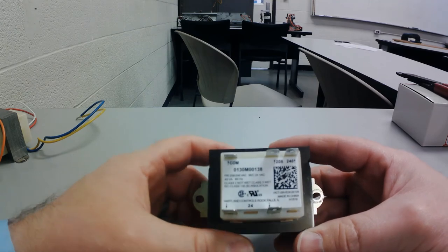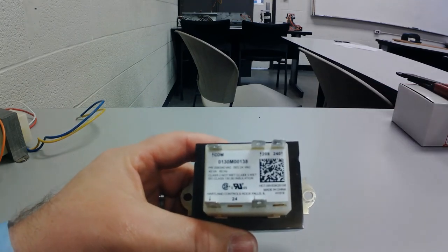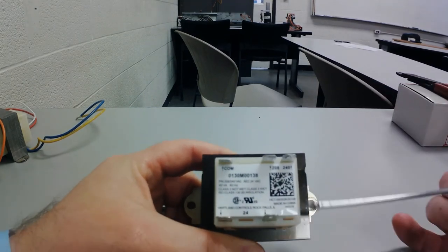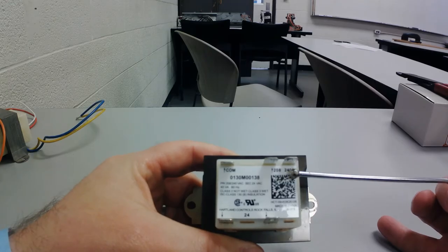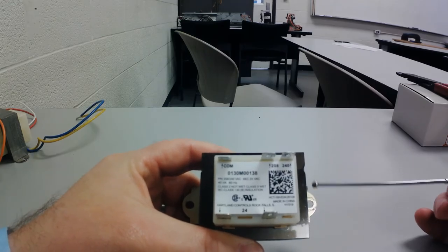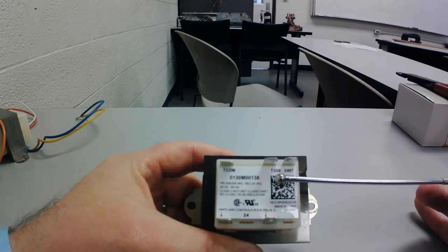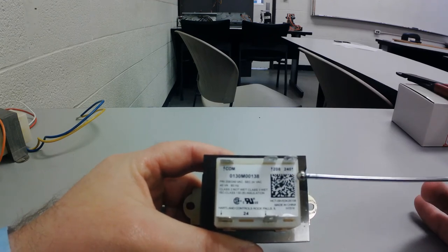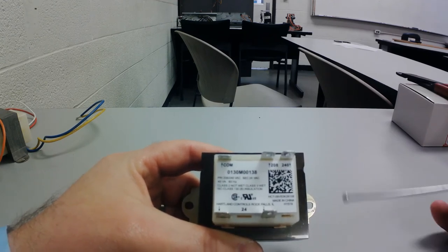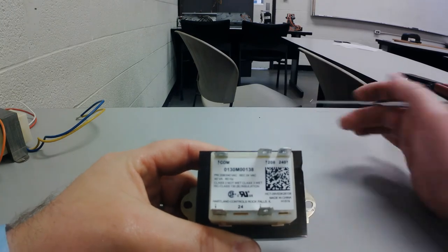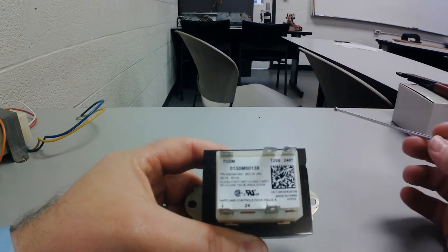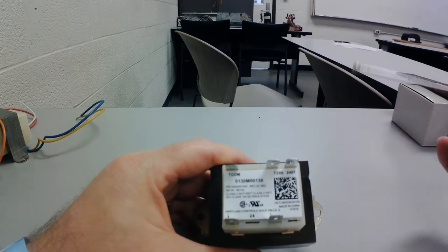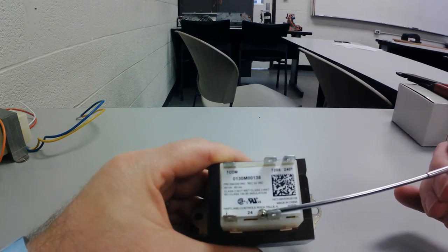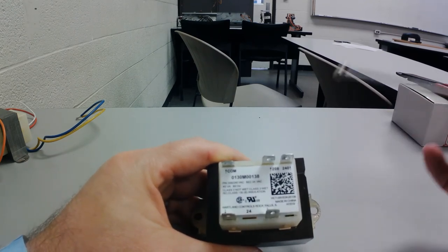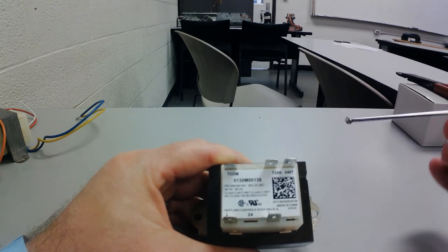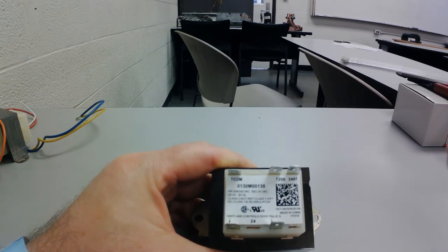2-voltage transformer, I'll call it. It's a multi-tap, is what a lot of technicians in the field will call it. But this is set up for 208 or 240. So this is not going to be in a furnace. It's probably going to be in a package unit. But you have two voltages that are very common in your single phase power sources for rooftop units, 208 and 240. We say that we get 24 volts out in the field, but more than likely it's between 27 and 28 on the units that you'll go to if the transformer is properly tapped.